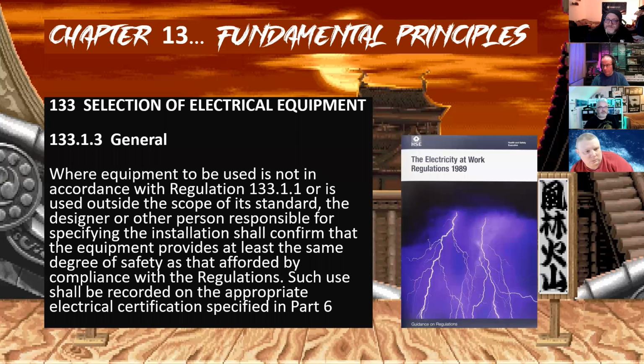Okay, moving on. Dave, go ahead. 133.1.3, general: where equipment to be used is not in accordance with regulation 133.1.1, or is used outside the scope of its standard, the designer or other person responsible for specifying the installation shall confirm that the equipment provides at least the same degree of safety as that afforded by compliance with the regulations. Such use shall be recorded in the appropriate electrical certification specified in Part 6.